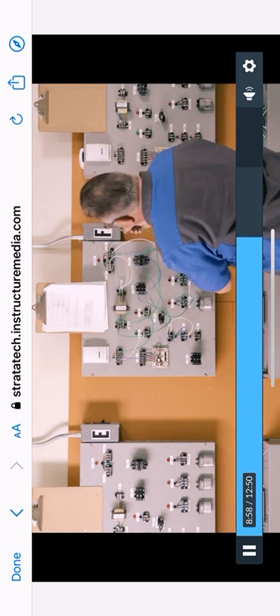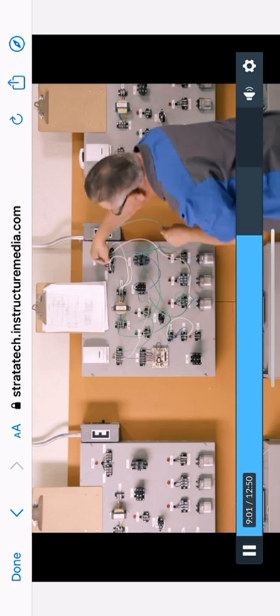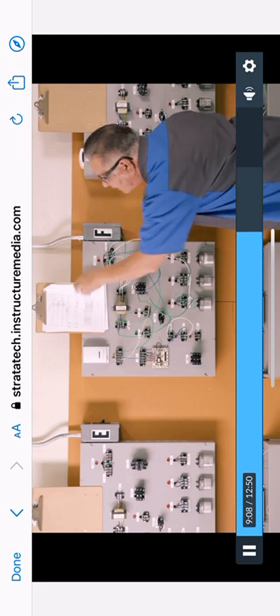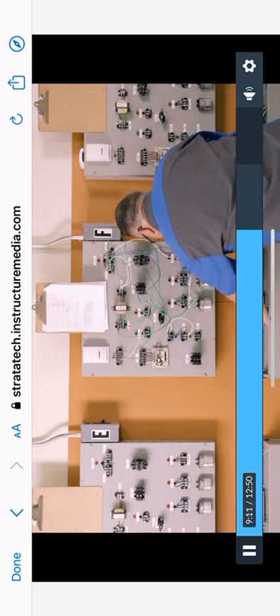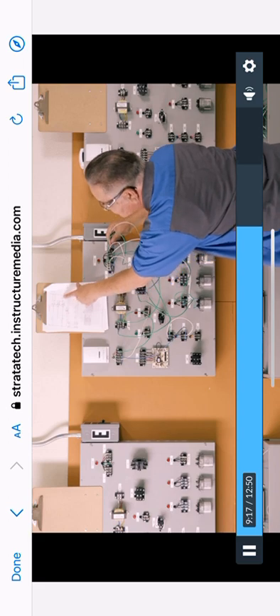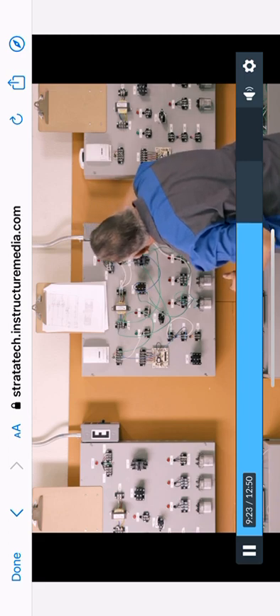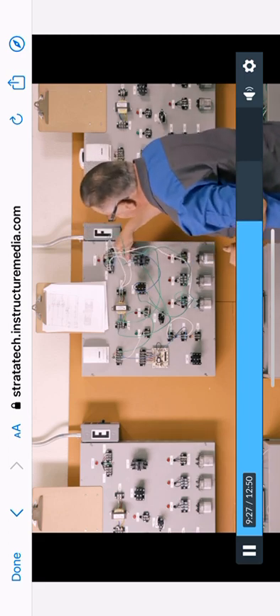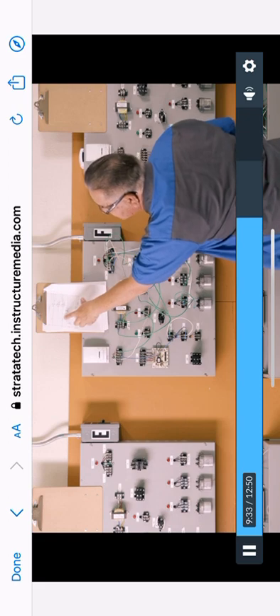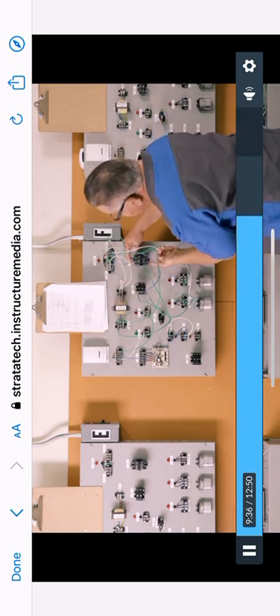So I'm going to go from line 1 to the top of my contactor, which is right here. Here's line 1. I'm going to put a wire on line 1, and I'm going to go to one side of my contactor on the top. Now I'm going to go to the other side, and I'm going to go from line 2, right here, to the top of my contactor. That's done. Now, I'm going to go to the bottom of my contactor, which is right here, T1. That's the bottom of, here's T2. Here's line 1. Here's T1. So that's what I'm doing right there.